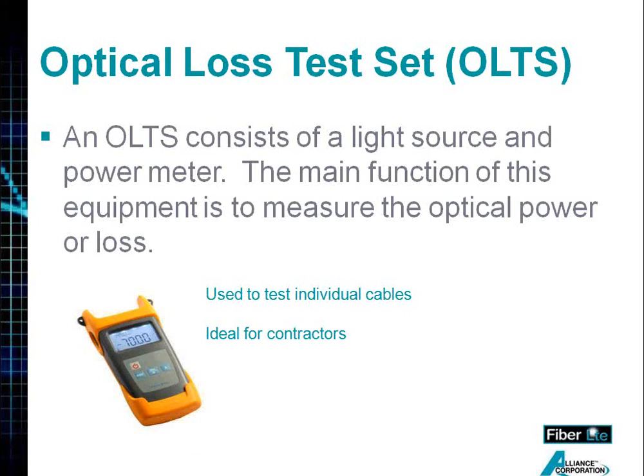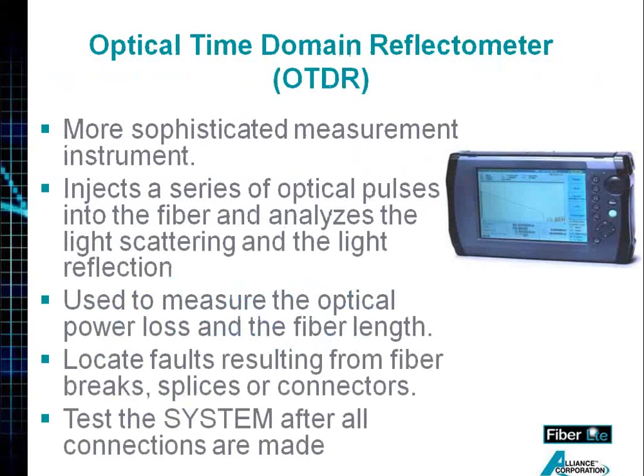Now, due to the relatively short lengths of hybrid or composite cables installed, the best piece of equipment required to test is a power meter and light source. Really, it's the only one stated in the telecom standard to certify an optical fiber. Multi-mode fiber loss measurements must be made using an LED source, whereas single-mode fiber loss measurements require a laser source. This equipment gives you a far more accurate value than an OTDR will. They're less costly and much easier to handle and understand.